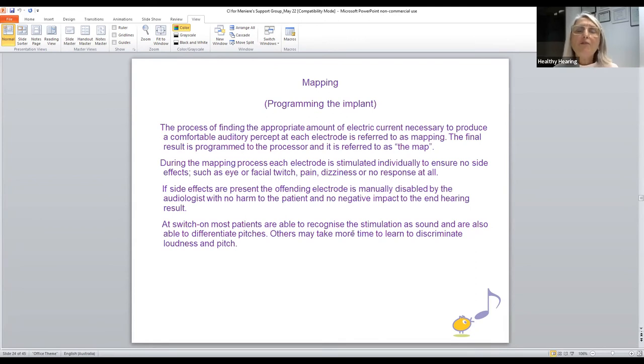So the process of programming, or mapping as we call it, is the process of finding out the amount of electric current required at each electrode to provide the recipient with comfortable hearing levels at every different pitch that each electrode provides. So we go through this process at the first switch on. We check each electrode, increasing the current until it's loud and comfortable.